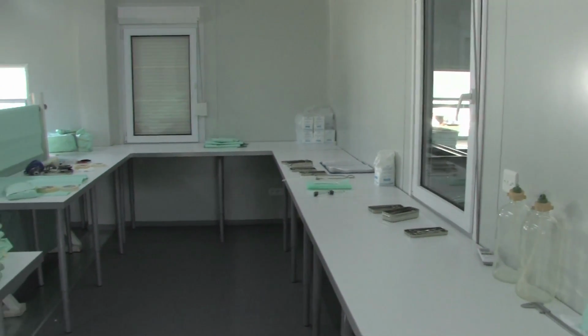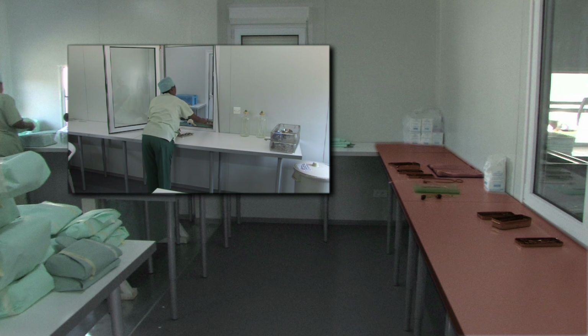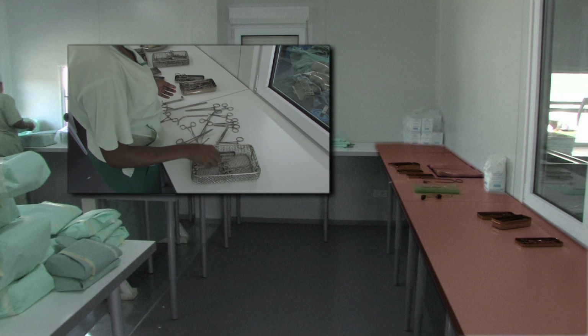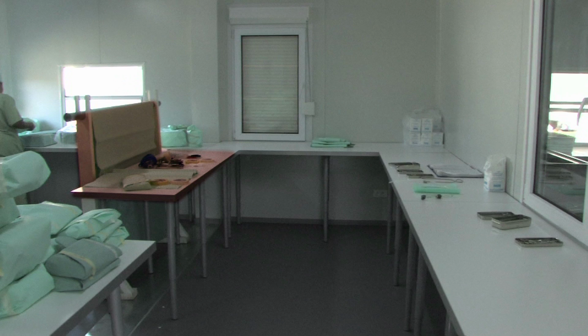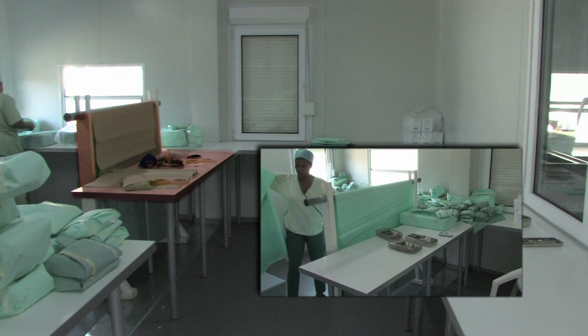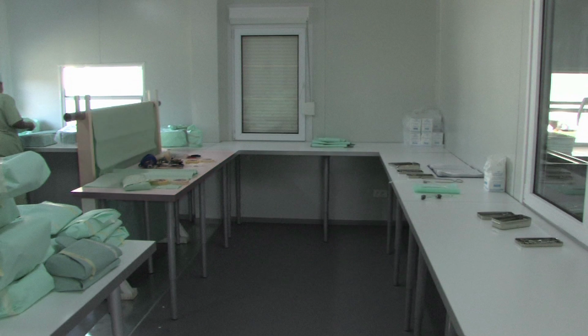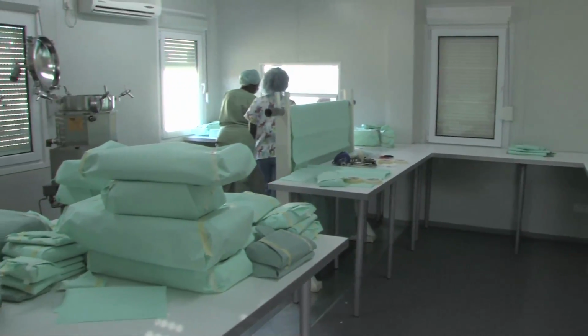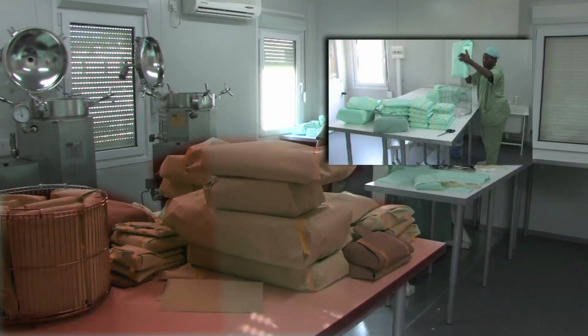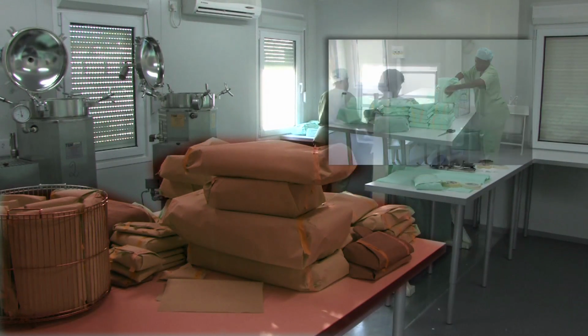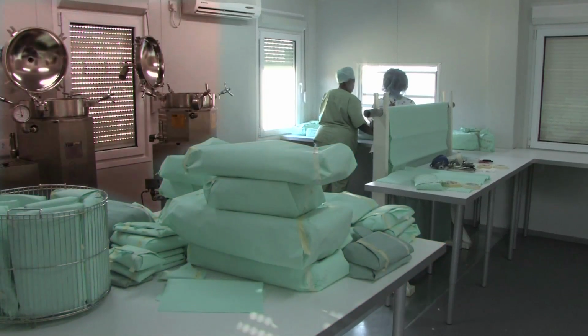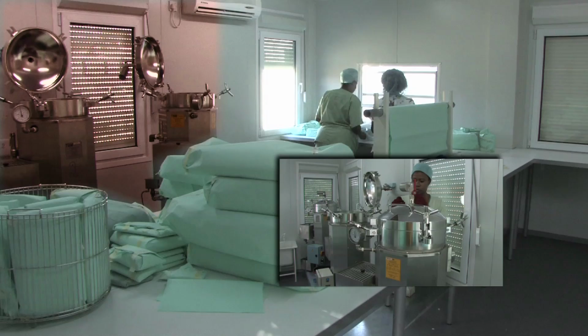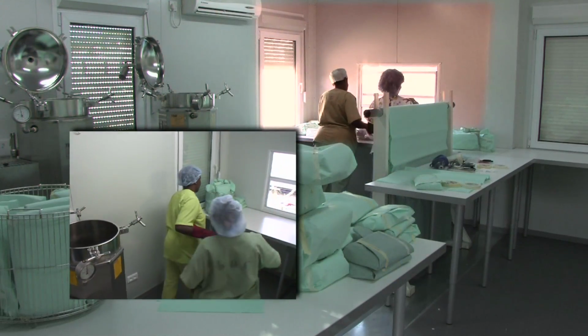The second room will have, at a minimum, a table for receiving clean, dry materials, which can be used for reassembling instrument sets, a packaging table with a cylindrical rod nearby for hanging sheets of sterilization paper, crepe paper or non-woven, without damaging them. For facilities with a high activity volume and several autoclaves, an additional large table that can be used to hold packs that are ready for sterilization. The second room also includes an area for the autoclave or autoclaves, as well as a table for putting down and checking the packs as they come out of the autoclave.